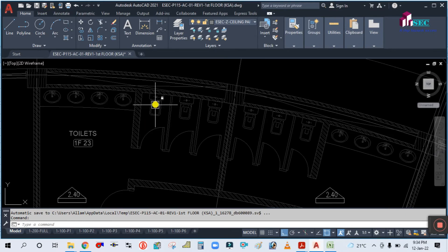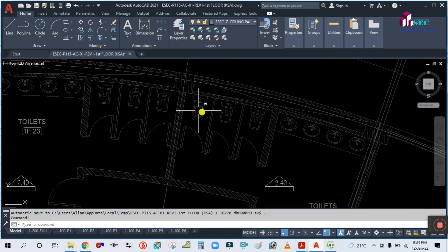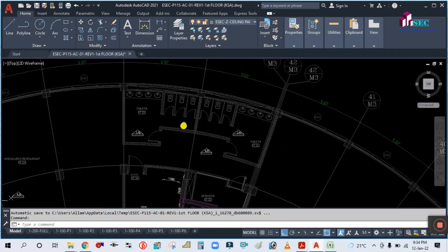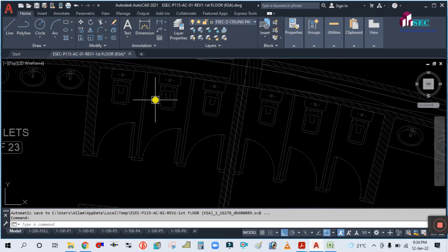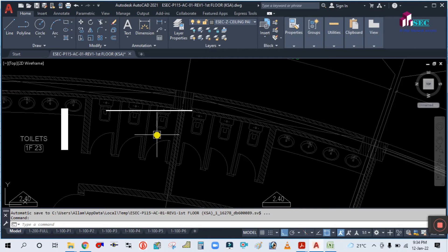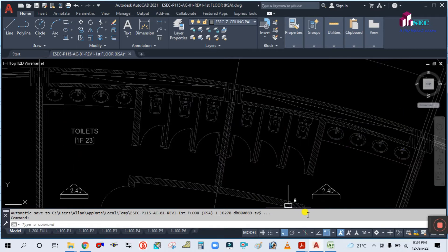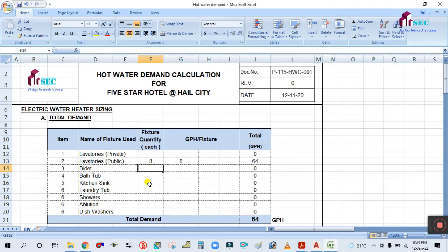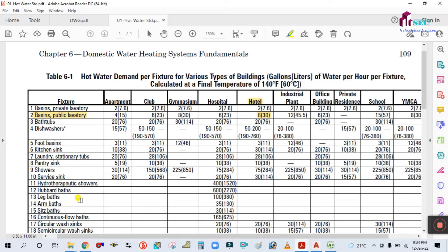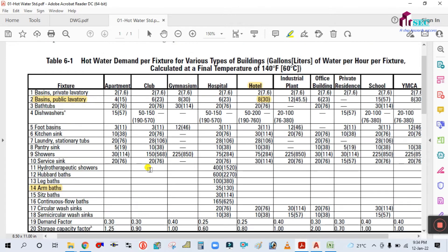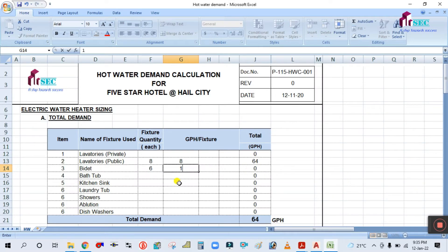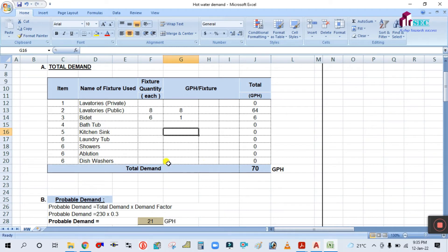You can see here there are 6 WCs, and each WC has one hand spray giving hot water — it is called a bidet — so total 6 units. For the bidet/arm bath, the GPH is looked up. If you see here this is arm bath — GPH is not given in the standard, so if not given, simply consider 1 GPH. So total demand is 70 GPH.